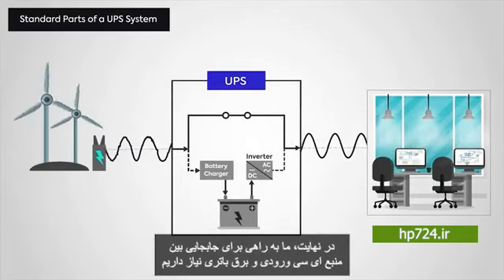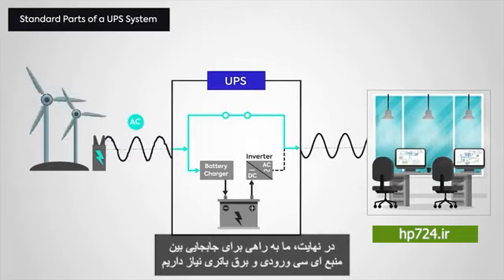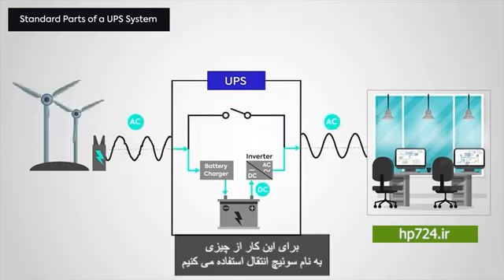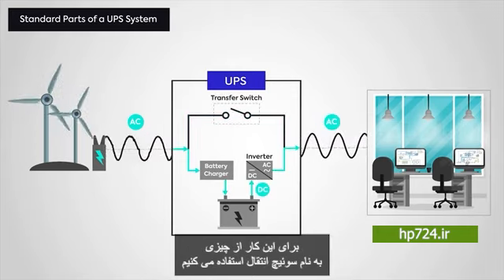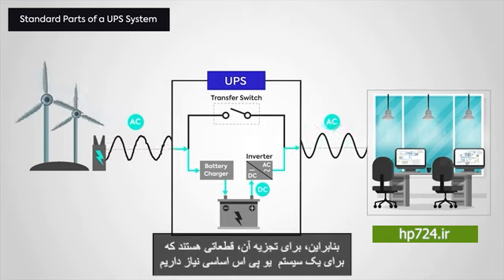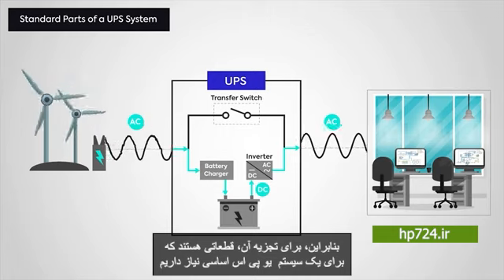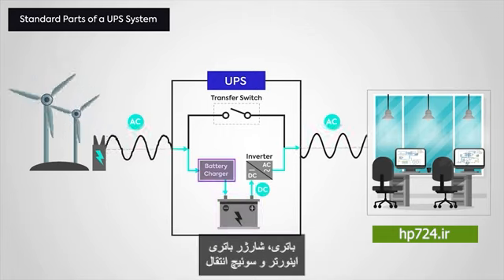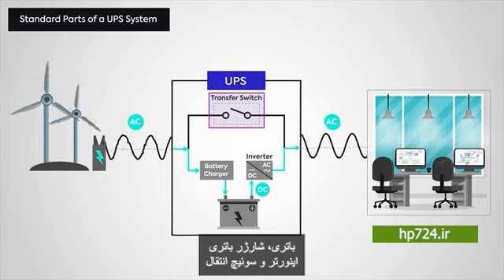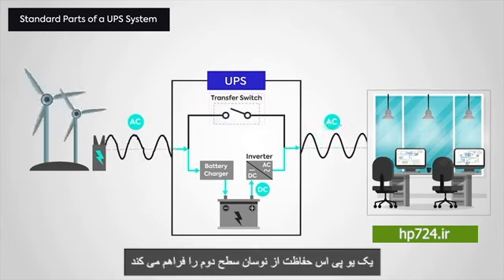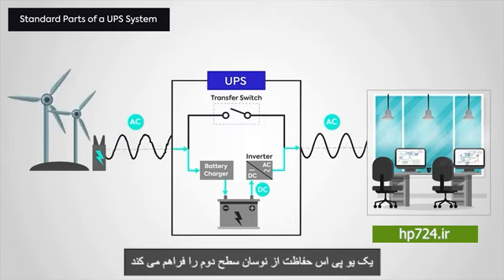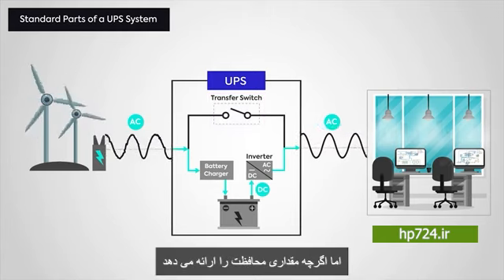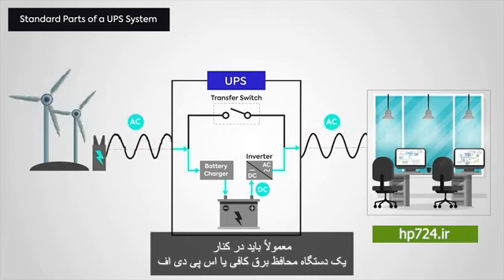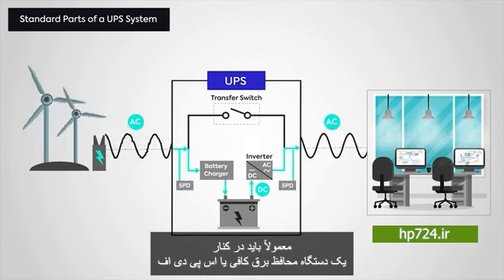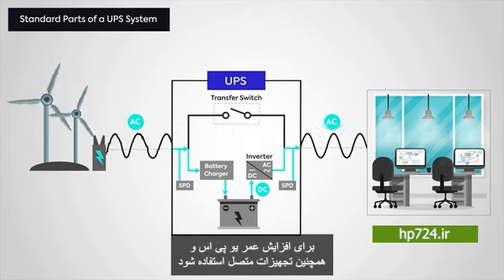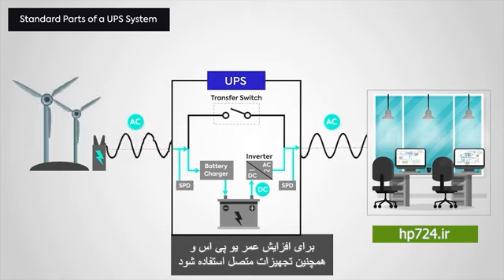Finally, we need a way of switching between the AC incoming supply and battery power. For this, we use something called a transfer switch. So to break it down, these are the parts we need for a basic UPS system: batteries, battery charger, inverter, and transfer switch. A UPS provides second-level surge protection, but although it does provide some protection, it should usually be used alongside an adequate surge protection device, or SPD, to extend the life of the UPS as well as the attached equipment. Sounds simple, right?